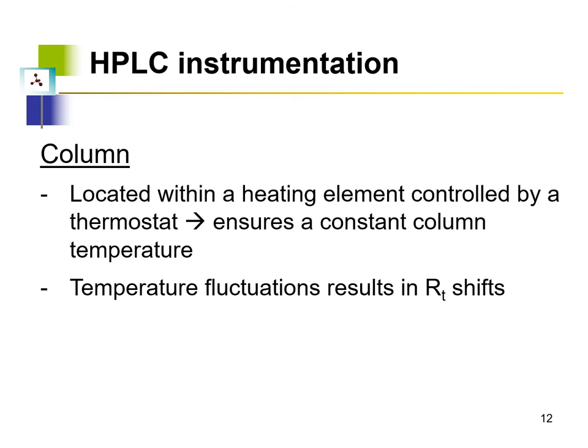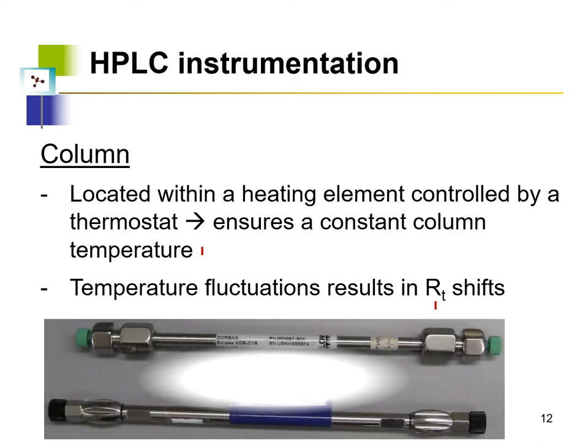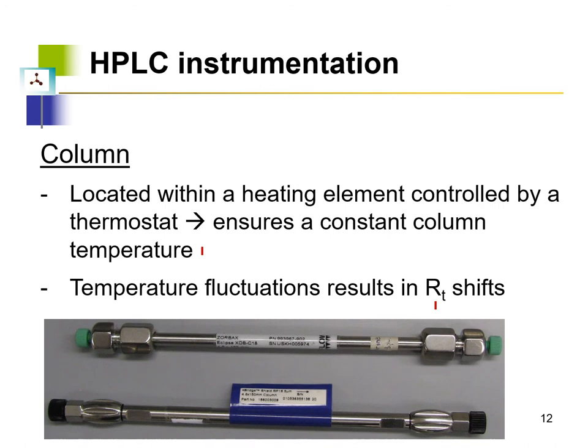The next component is the column, which, similar to a GC column, is located within a heating element where its temperature is controlled. Temperature affects the retention times of chemical components, so the column must be maintained at a set temperature — typically 30 or 40 degrees Celsius — to ensure reproducible retention times across runs. HPLC columns are much shorter than GC columns; common lengths include 5, 10, 15, and 30 cm.